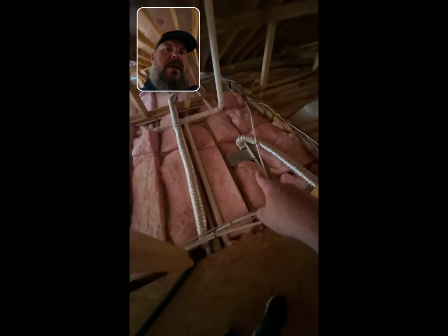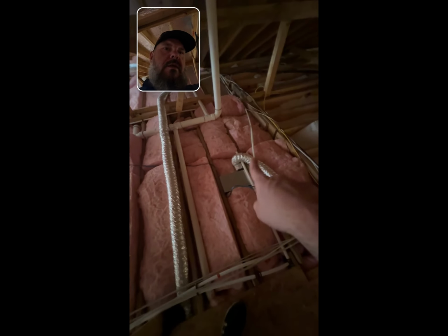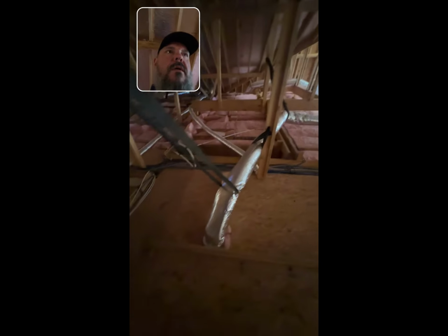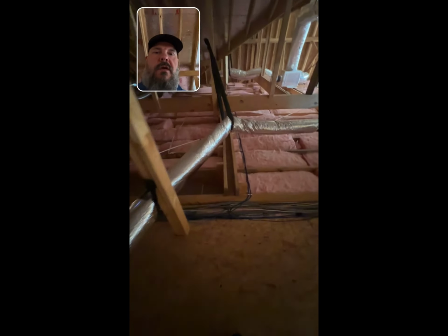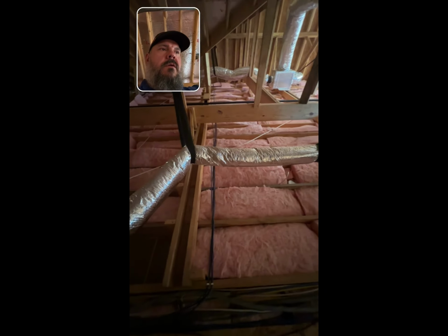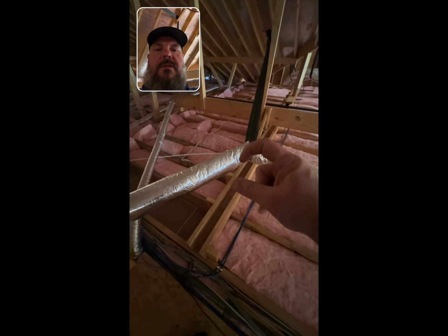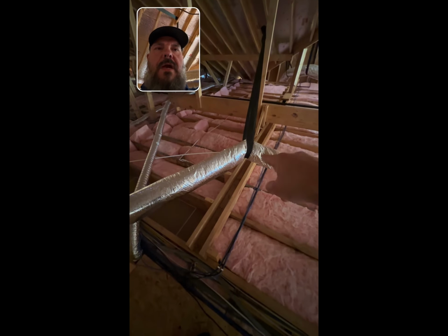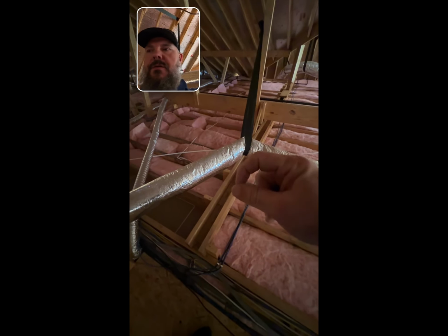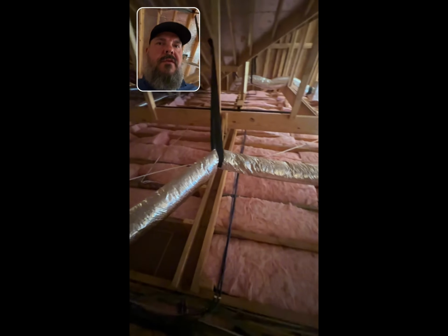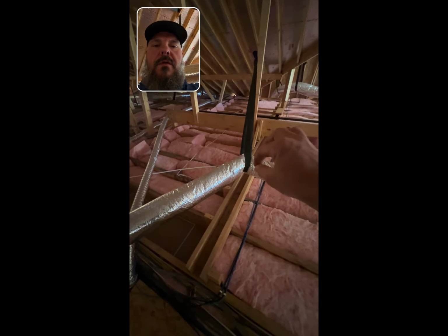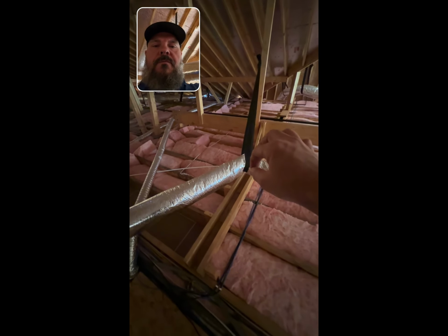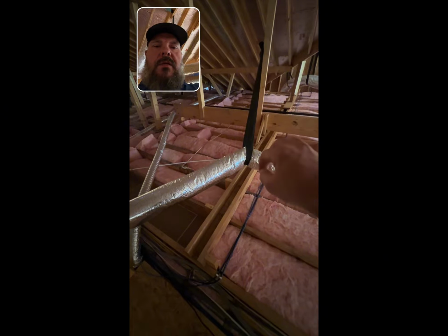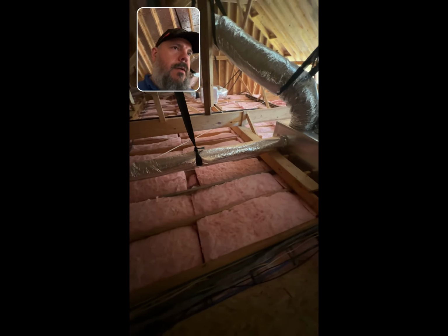So once again, we have another bathroom vent that's ducted the opposite direction, and it runs just once again haphazardly across the attic. On this system, we have kinked off ductwork. So this duct is an R8 insulation, which is fairly thin, and then when you strap it, pull it tight, you collapse the insulation. These systems have 52 to 55 degree air running through them. That's a point where the surface will reach dew point, and it will start to condense and then drip water onto the insulation, the attic floor, and eventually through the ceiling.